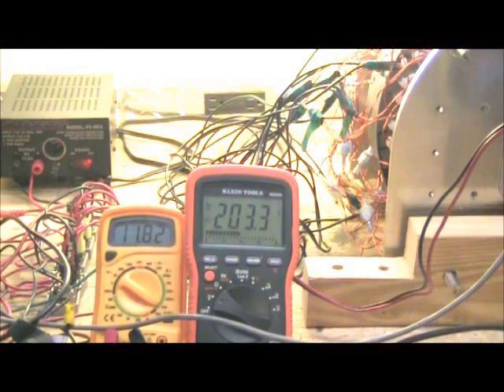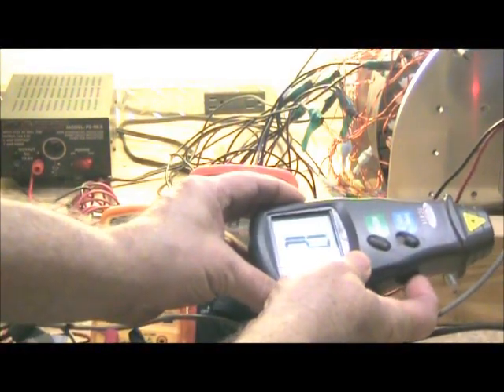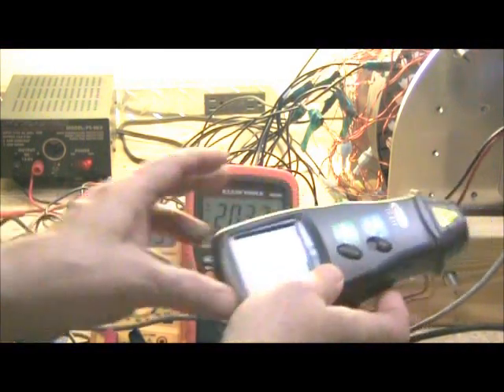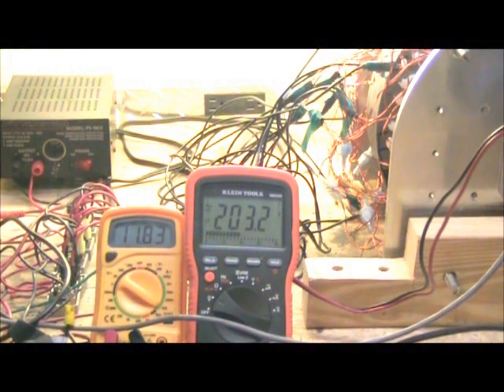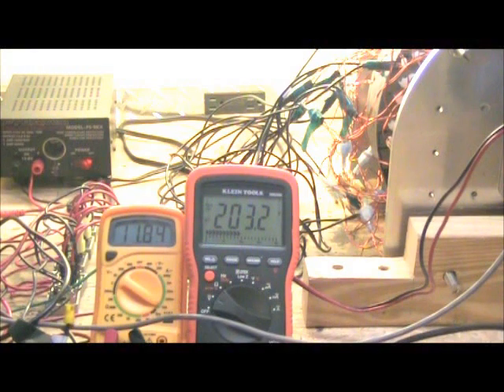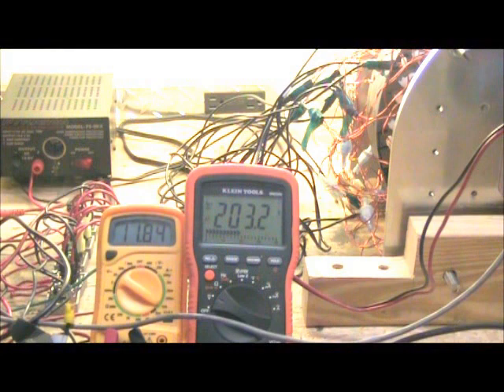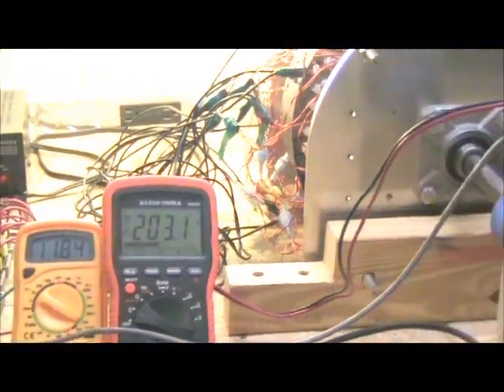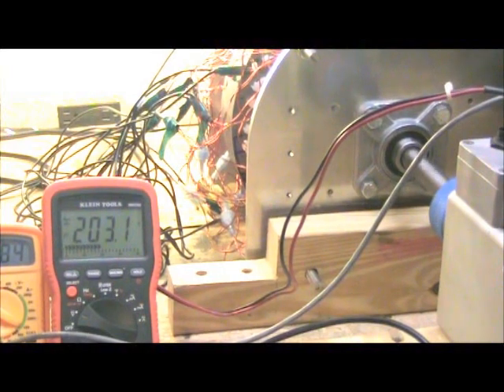So I put that information in the spreadsheet. I'm going to monitor the RPM. It's running 1195. We're at 15.2 amps. Now what happens is the drive can't keep up with it.